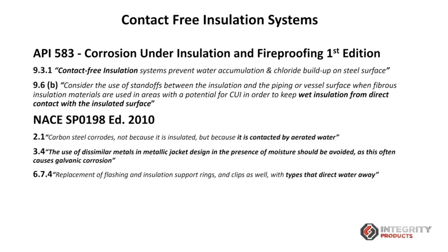And also in another clause, 9.6b, in the last part of the sentence, it says keep wet insulations from direct contact with the insulated surface. So that means this document is again and again emphasizing the need for a contact-free system for the insulations. Moving back to NACE SP198.